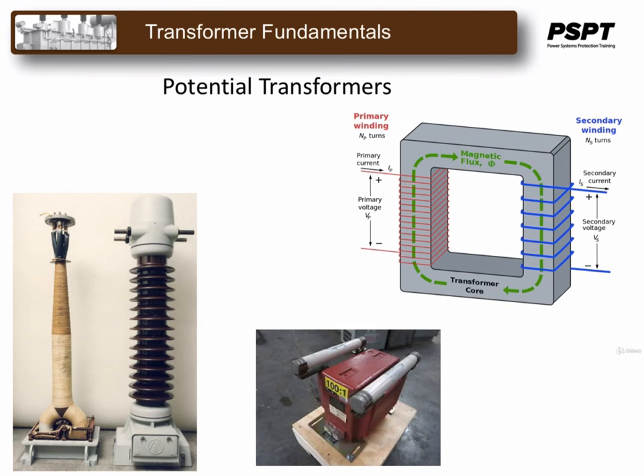For potential transformers, in general, the ratio of the secondary voltage to the primary voltage is governed by the turns ratio of the windings of the transformer. This relationship is not completely exact for the following reasons. The excitation current that is necessary to magnetize the iron core causes a small impedance drop and a phase shift in the primary windings. The load current that is drawn by the burden also causes another small impedance drop.